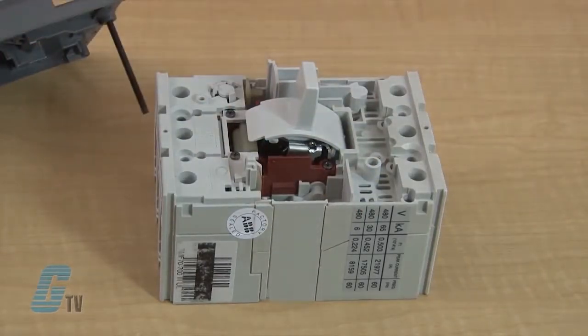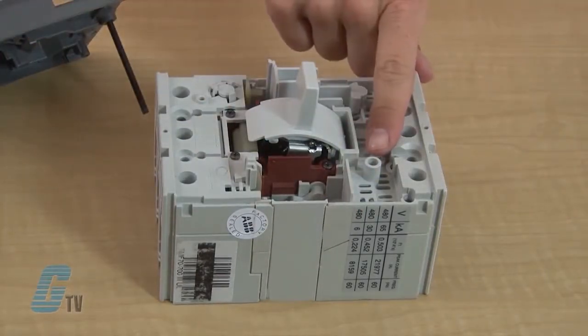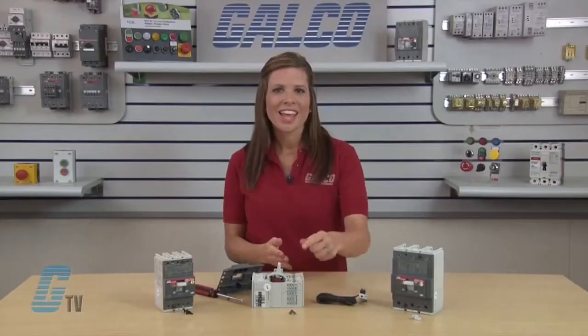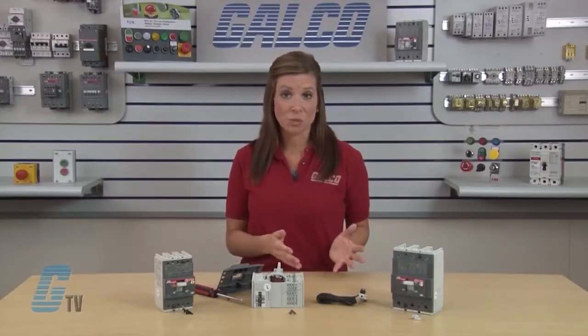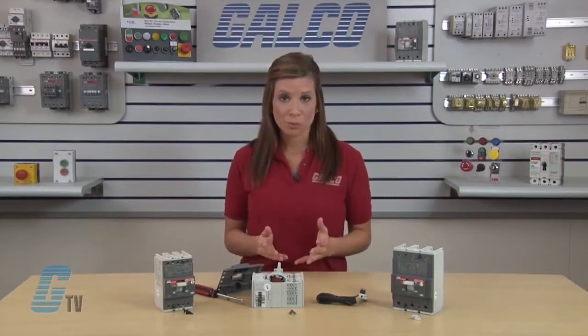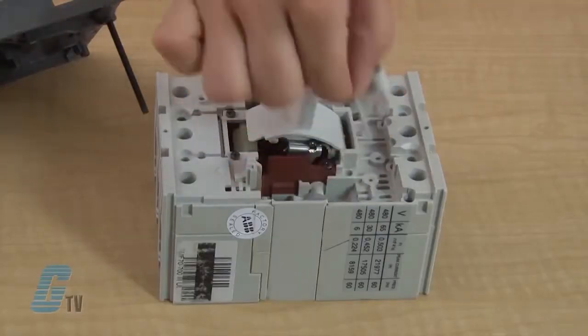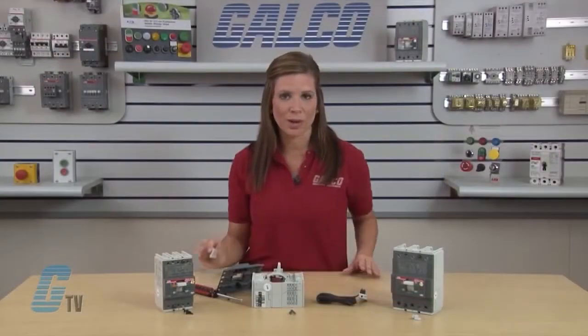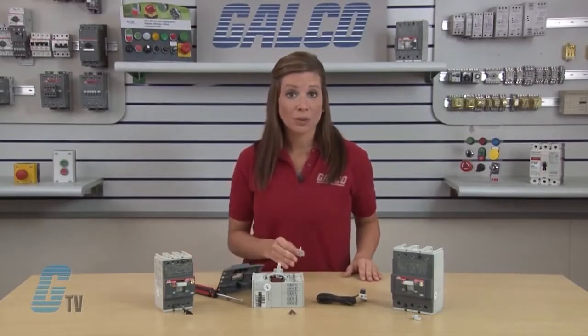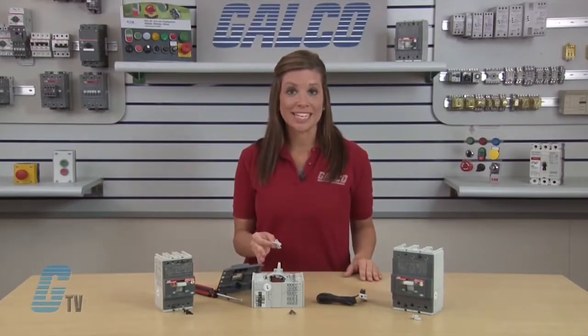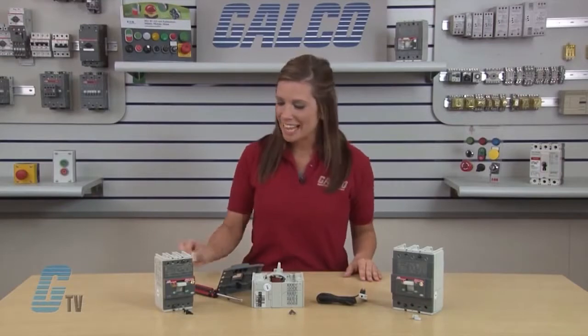As you can see, the T2 model has a protective cover where this accessory will go. This cover is not present on the T1 or T3 models. To remove the cover, I will gently grab it by the tab and easily pull it straight off. This cover will not be used once the auxiliary contact unit is installed, so I will set it aside for recycling.